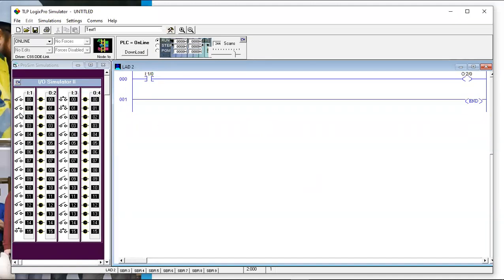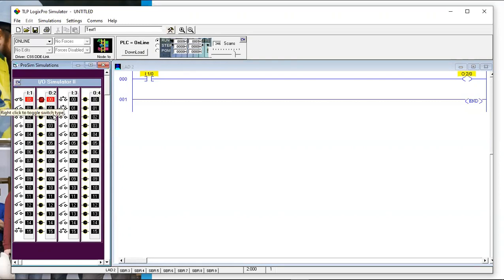In order for it to work, we download it to the processor and put it into run mode. Let's close the switch and see if it works. It did. We closed the switch, it made the input instruction true, which made the output instruction true, which turned on the actual real-world output and lit the light.